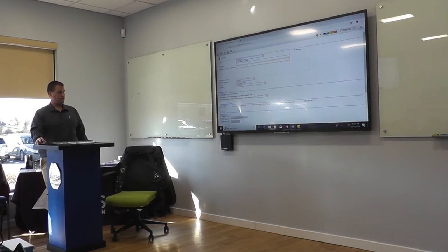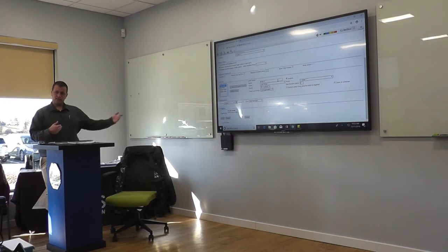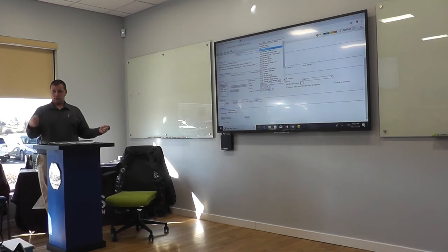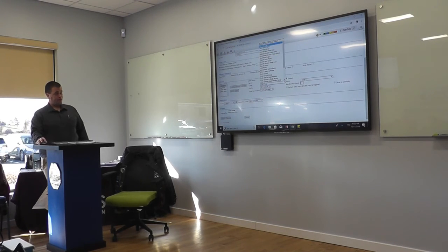So you could create an event in the system, and then there are a number of different actions that you can apply to that event, one of those being an email. These are the different types of actions you can associate with an event. When that event gets triggered, say by a door getting accessed or forced open, you can have the event do something other than just pop up on that screen.